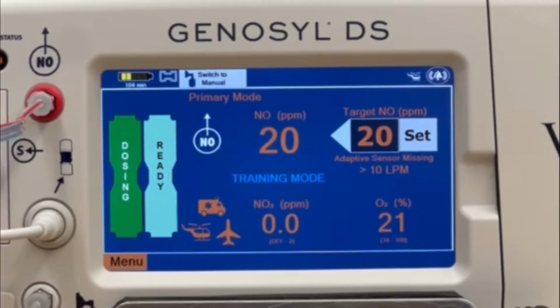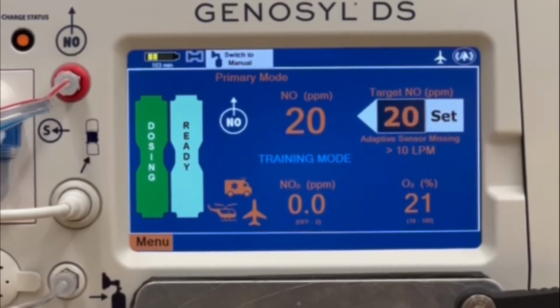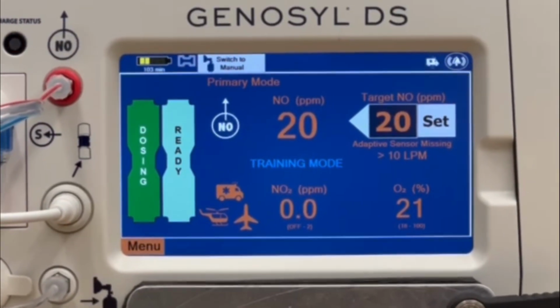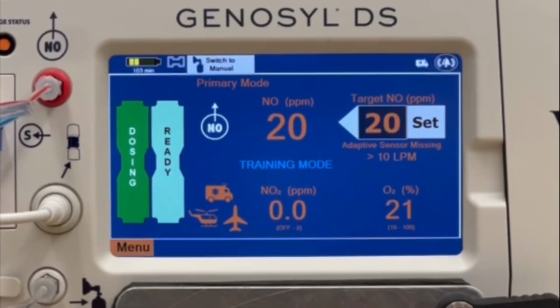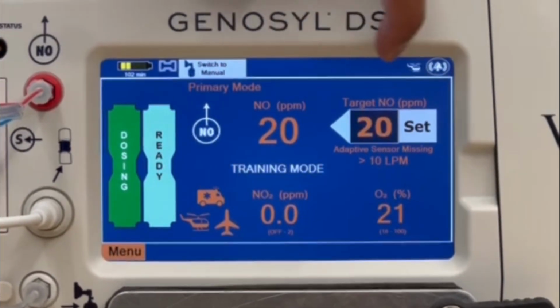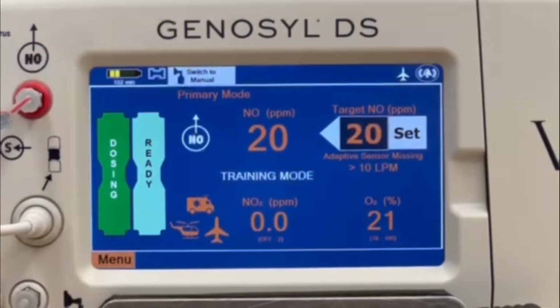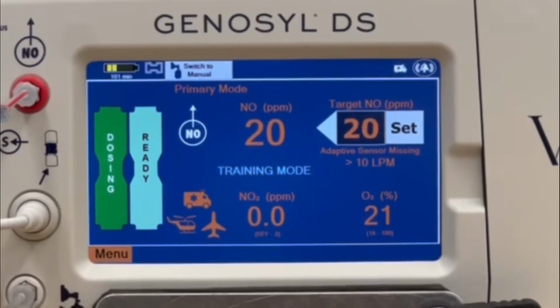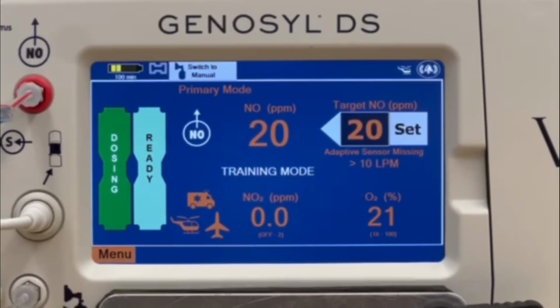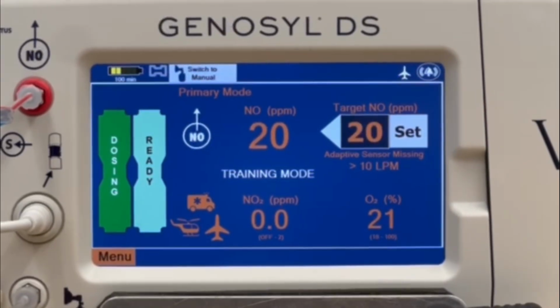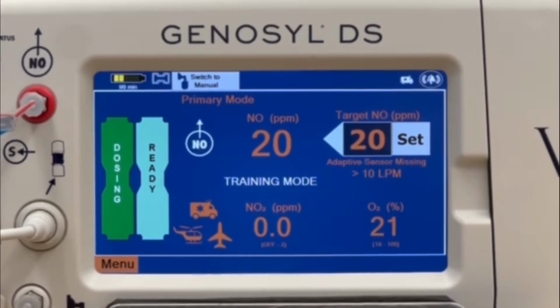You can also access the troubleshooting part from the alarm itself. So I'm going to make an occlusion alarm. Once we have an alarm pop up on the screen itself, you can tap it and it will take you directly to those troubleshooting steps. That way it gives you all that added benefit of information so you can quickly troubleshoot during your transport if something does come up.